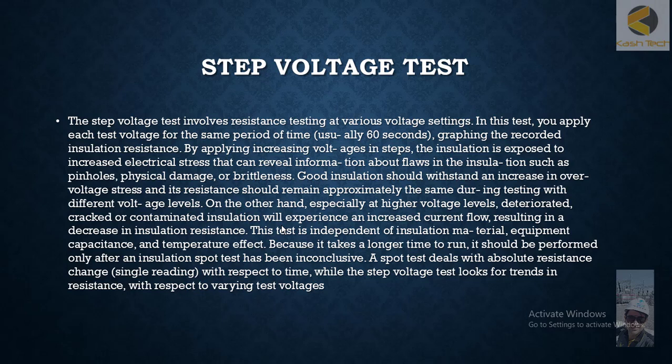The insulation is exposed to increasing electrical stress that can reveal information about flaws in the insulation, such as pinholes, physical damage, or brittleness. Good insulation should withstand an increase in applied voltage stress and its resistance should remain approximately the same during tests with different voltage levels. On the other hand, especially at higher voltage levels, deteriorated, cracked, or contaminated insulation will experience an increased current flow, resulting in a decrease in insulation resistance.